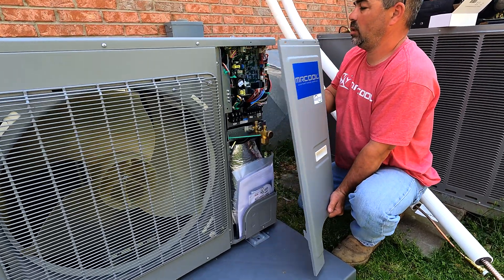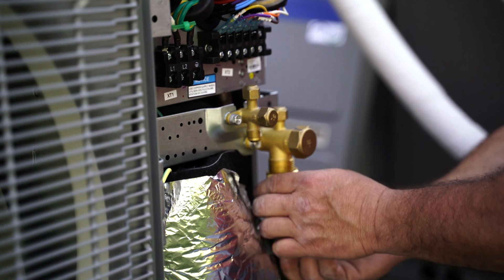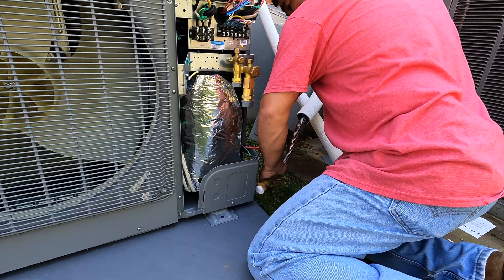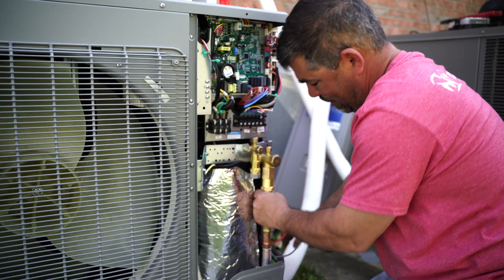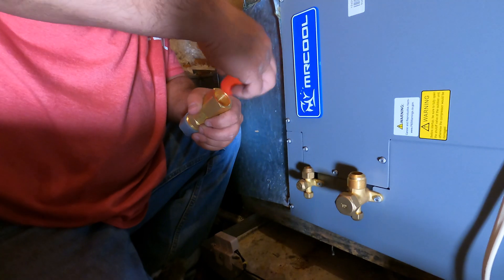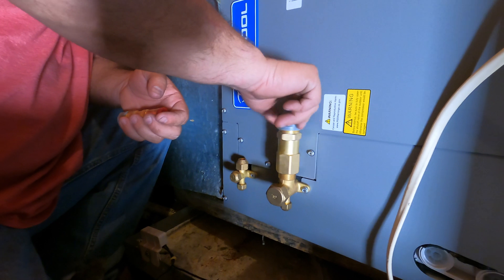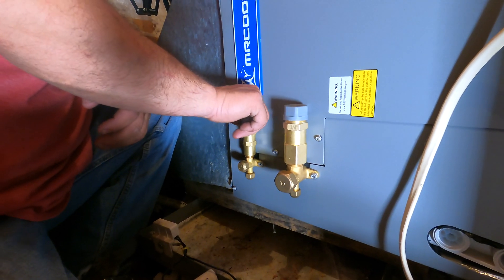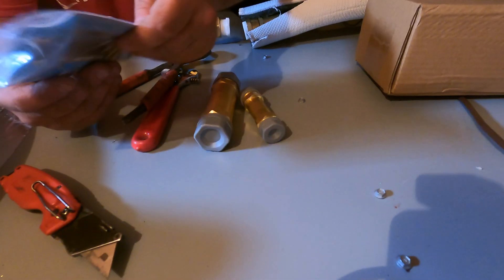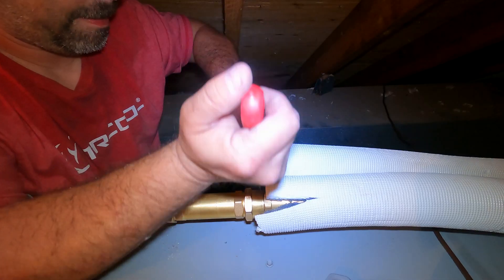At the condenser we connected the quick connect fittings, then screwed on the MRCOOL quick connect line sets. At the A-Coil in the attic, we added the quick connect fittings. Then we connected the 15 foot line set and the 35 foot line set together using the Mr. Cool coupler kit.